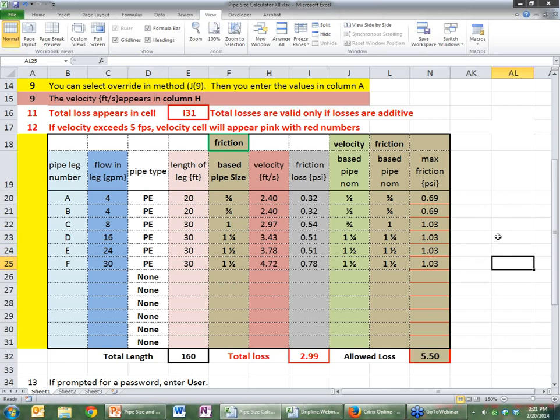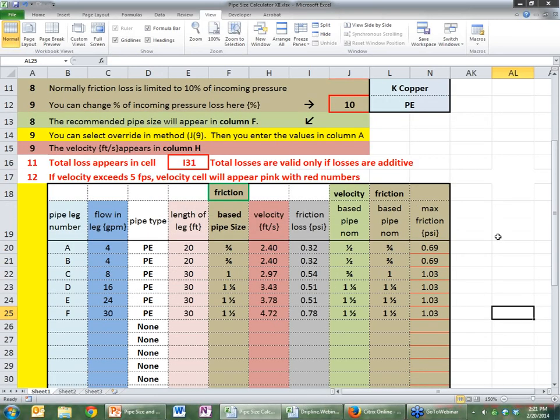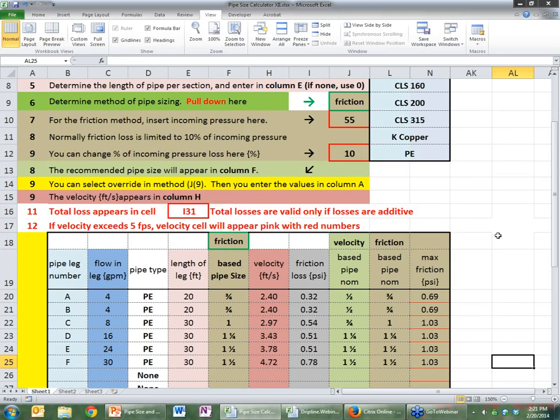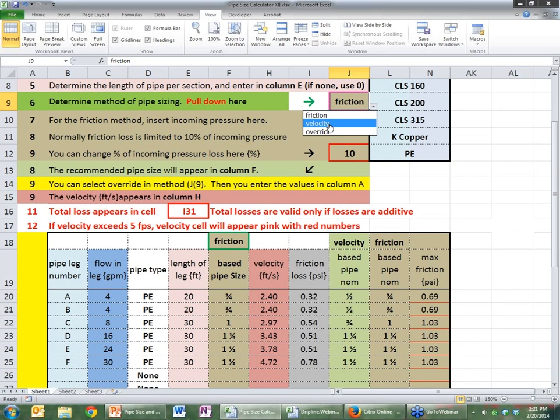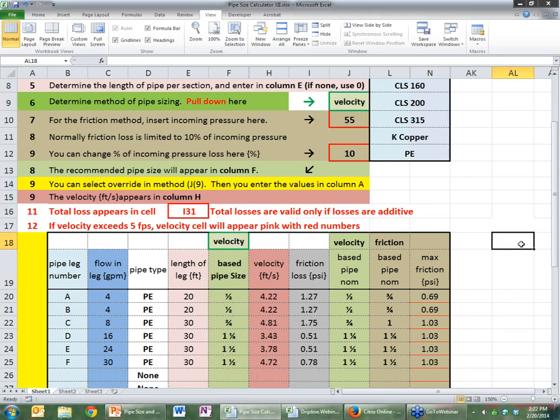Because I think many of you, or at least I'm talking to people, lots of people who are using PE. And you'll see things change significantly, both in sizes and in velocities. Now the velocities in this last section are still fairly high, but using the friction method, 2.99 out of 5. Now once again, if we wanted to, we could override that and say I'm only going to use, and you could say here, well I'm only going to use one inch and inch and a half in polyethylene. We could also look at it velocity based, and here it is velocity based, and notice that the pipe size has changed.